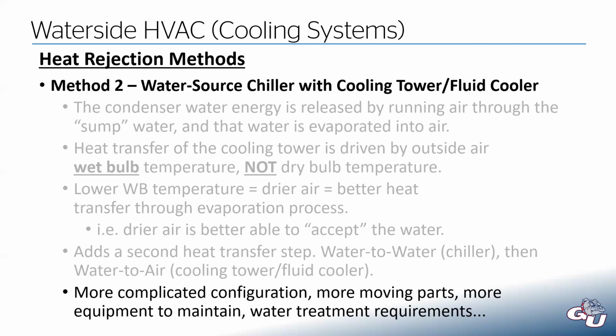What if you live in a climate where you have to be worried about freeze protection issues? In the winter, is that water in the tower going to freeze? And if it is, like in Spokane, we would have to figure out what to do about that. One method is you just drain the tower every winter, and then you just don't have cooling. But maybe that's fine. A lot of times we don't need any cooling in the winter anyway, so no big deal. Another way to do it is at the bottom of the basin, you stick in some electric resistance heaters that will keep that sump water at a minimum temperature, keep it from freezing.